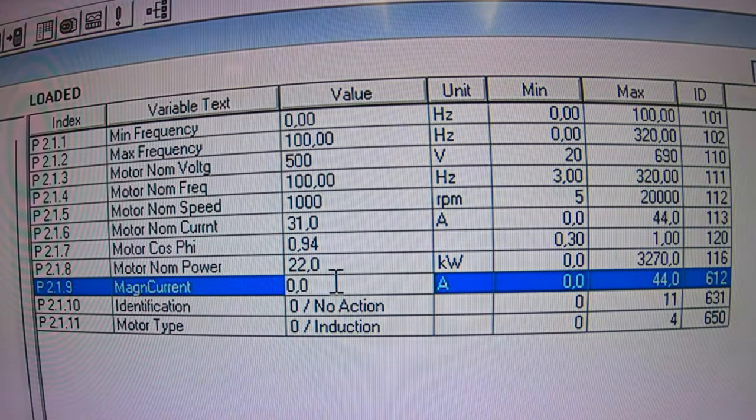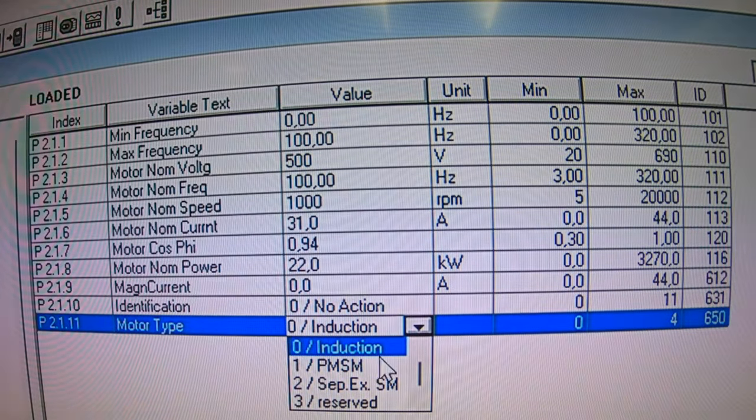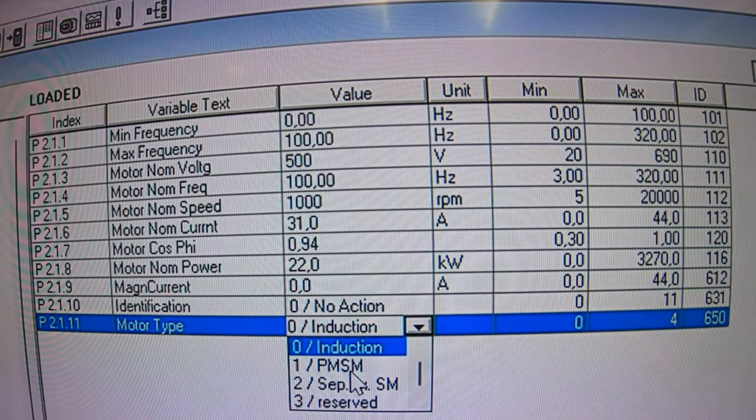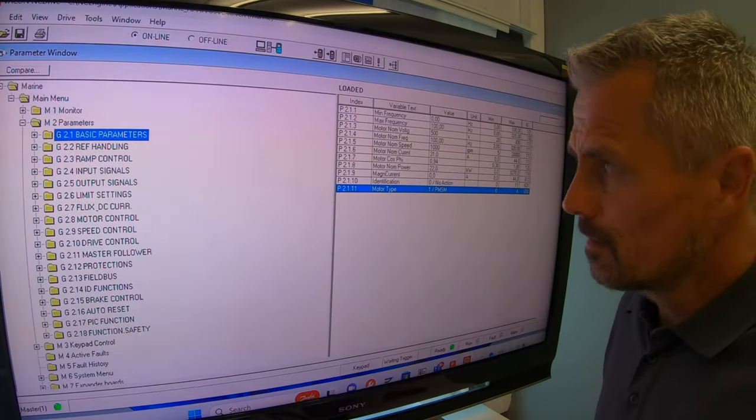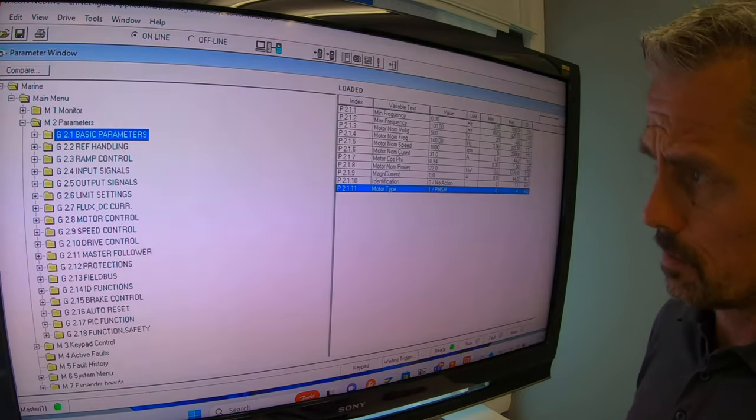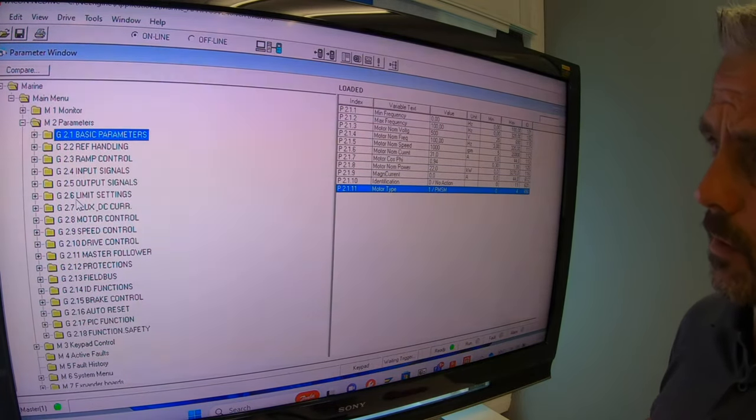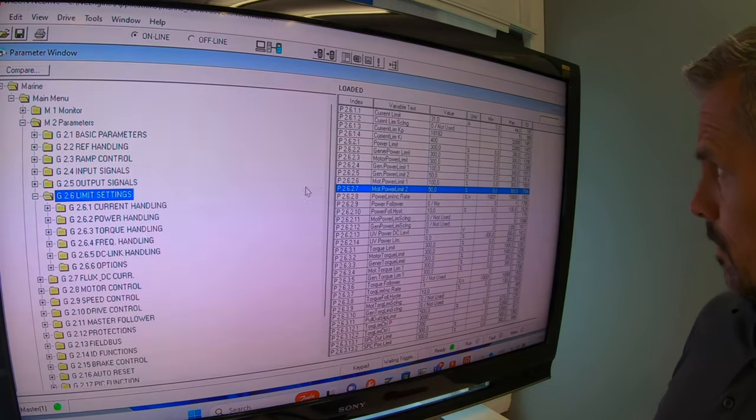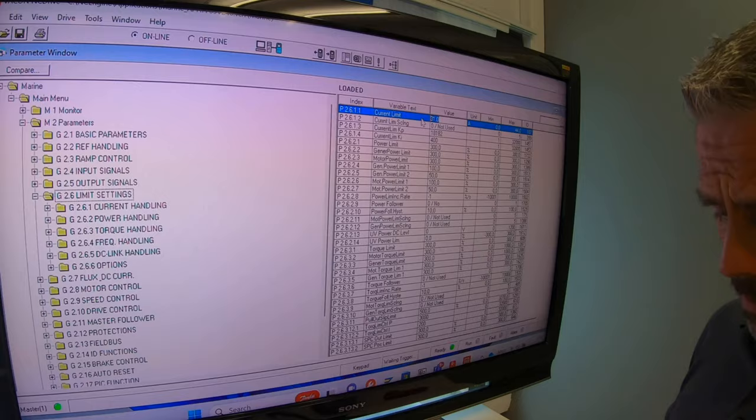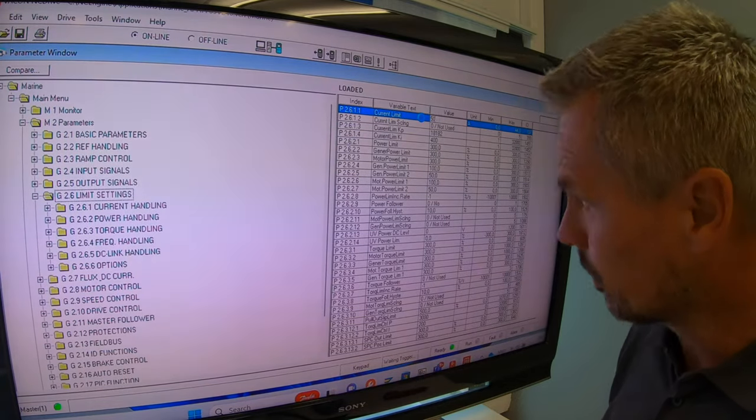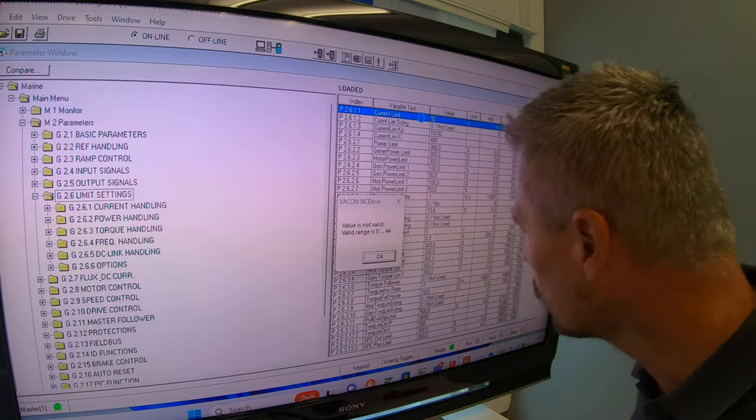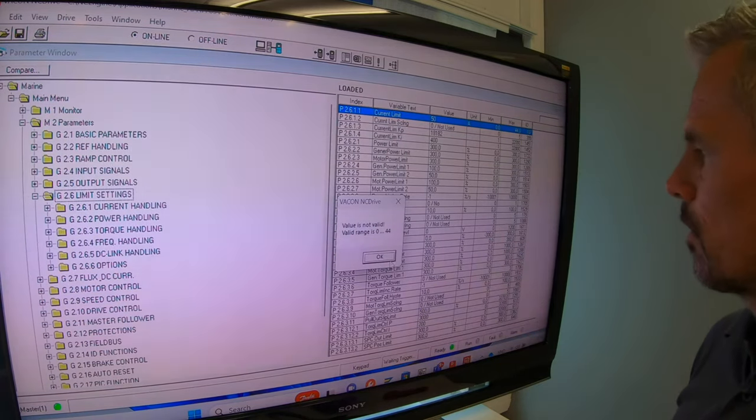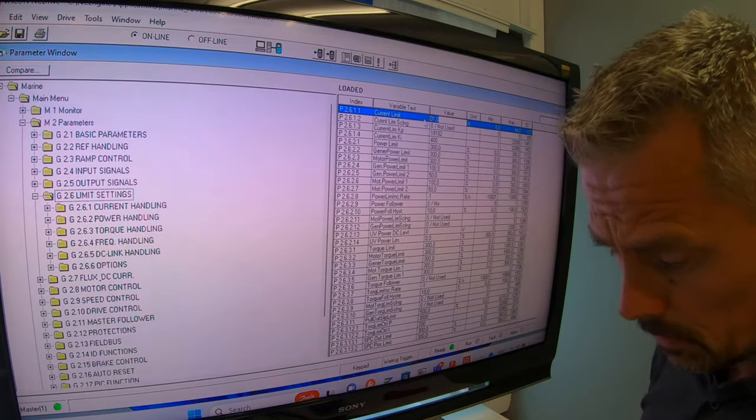Magnetizing current - this is not the induction motor, so nothing. Motor type, I select PMSM, that is Permanent Magnet Synchronous Machine. There are also other parameters I want to have a look at before I start any tuning. The current limit here is 31 ampere. I want actually the maximum which this drive can give. If I try to give it 55 amperes, no - 44 is the maximum. I want all of those amperes when I'm doing tuning.